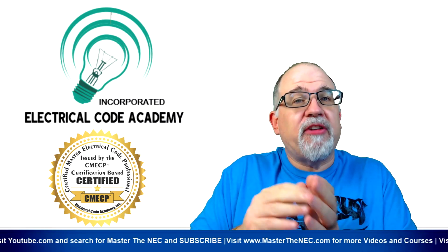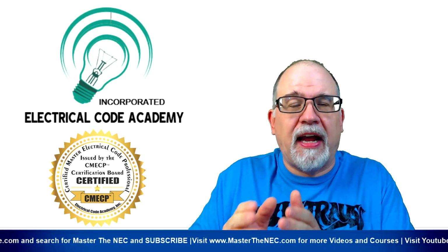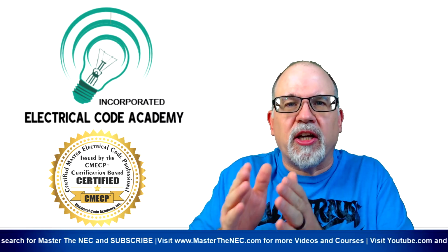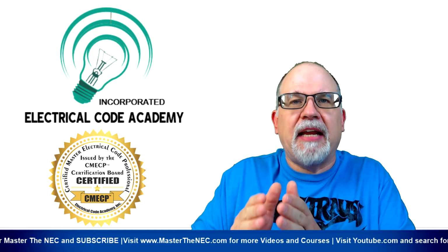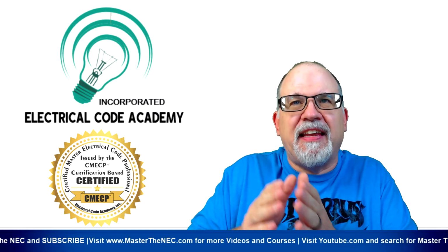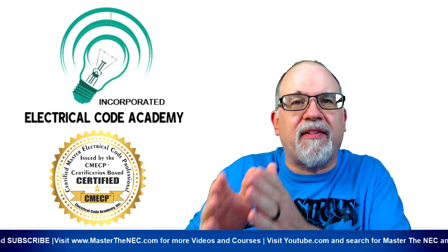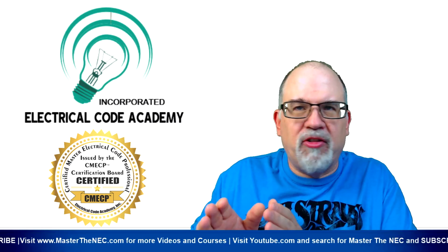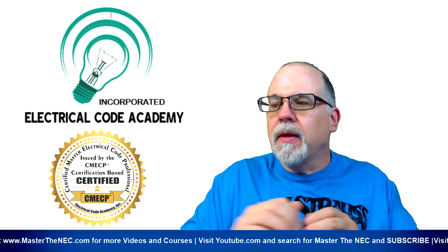Now, I still have to protect those secondary conductors, and I have to install them in accordance with the secondary conductor rules. And if they terminate in an overcurrent device, they have to be rated at least equal to the equipment or the overcurrent device that they terminate into. That didn't change. That's all the same. But let's talk about the table.